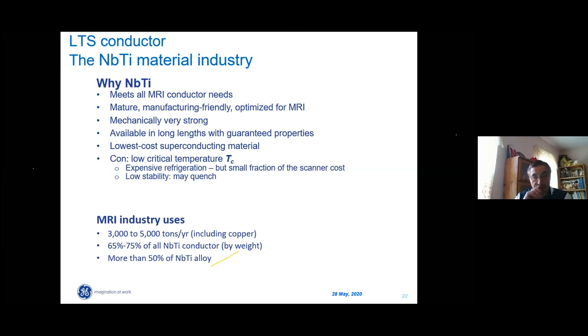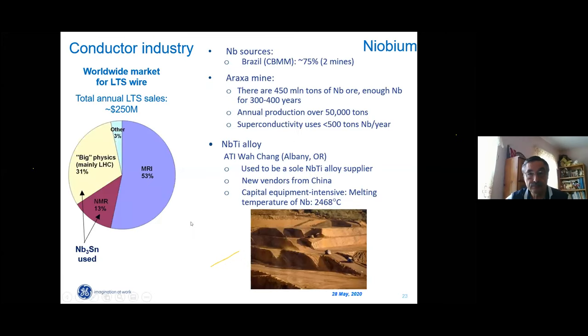Just a few numbers on what the MRI industry uses. We use about 3,000 to 5,000 tons a year of superconducting wire, and this includes copper. In terms of niobium titanium, the number is on the order of 500 tons a year. We use about 2/3 or 3/4 of all niobium titanium conductor by weight, and more than 50% of niobium titanium alloy. The major source of niobium is Brazil, the so-called Araxá mine, where two mines supply about 75% of niobium worldwide.